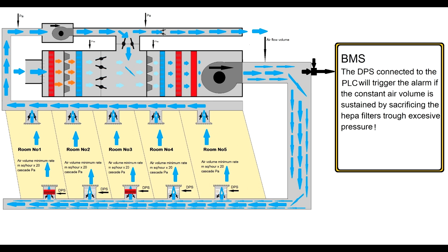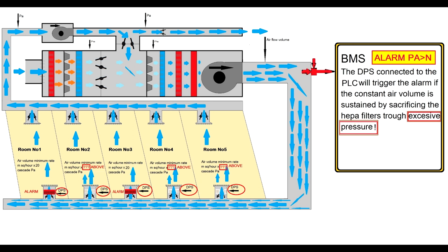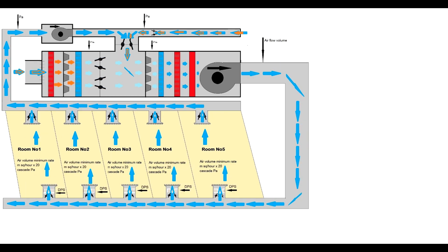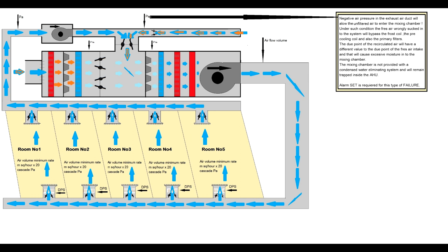But if the filter gets red, then it's an alarm. An imperfect system without the differential pressure switch across the HEPA filter will not work well. The main sensor in the duct will send the BMS an input telling me there is not enough airflow in the duct, and will sacrifice the filters by increasing the pressure in the system. I'll speak about this later on. One of the other biggest dangers: if you increase the fan speed, the supply fan, you can increase the airflow, and air might start to come back through the exhaust.